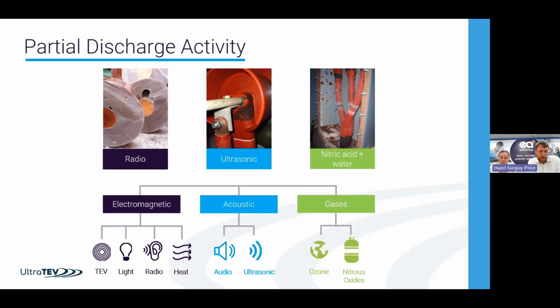That speed of the pulse is helpful because it gives us a broad range of energy in the radio frequency area, and we use a technique called TEV, transient earth voltage, which is basically looking for that fast pulse as it travels to ground across the surface of the switchgear.